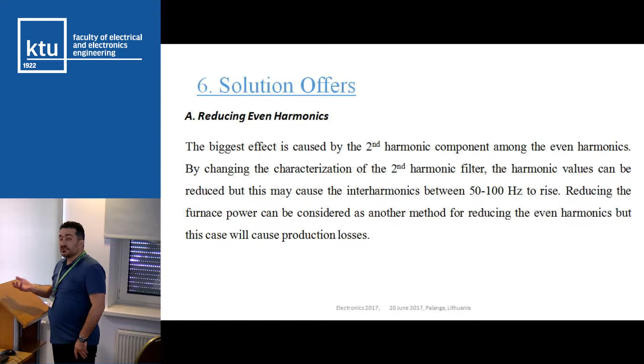How can we reduce the even harmonics? First, even harmonics are a problem for us, and we must reduce them. For that, we can reduce the transformer power for the arc furnace, but this is not a good option for us, because the arc furnace load will have some production losses. The second solution is increasing the short circuit power of the grid.